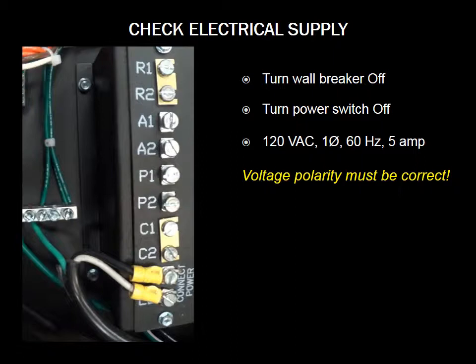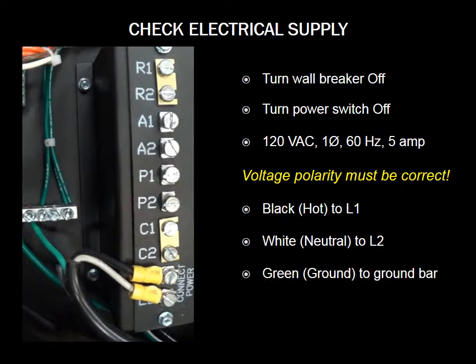The CONQUEST control system is polarity sensitive. Electronic flame sensing requires correct polarity. Be sure that the hot side of the 120 volt AC or the black wire is connected to terminal L1, that the neutral or the white wire is connected to terminal L2, and the ground or green wire is connected to the ground bar. Visually and physically check that all electrical connections are tight by lightly pulling on the wires. Retighten any loose connections.